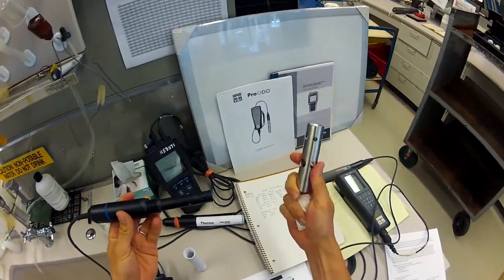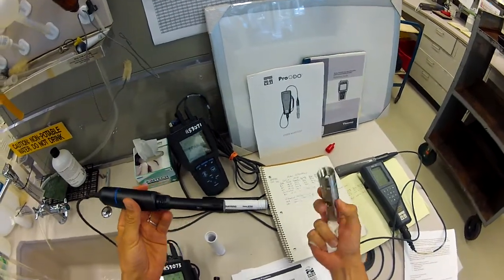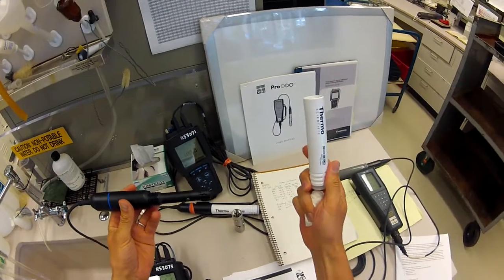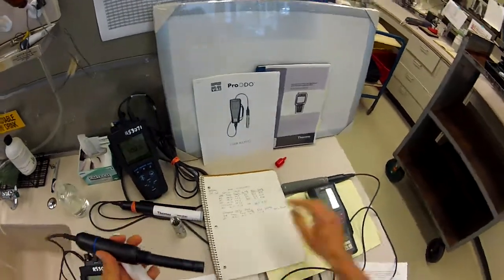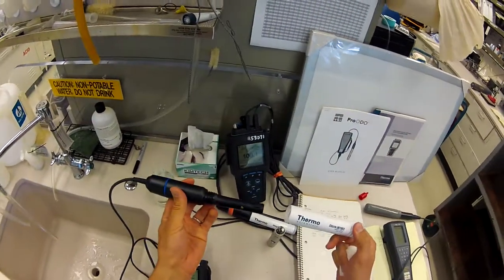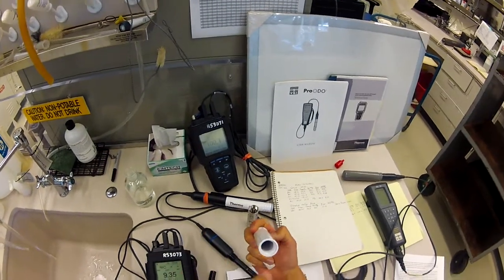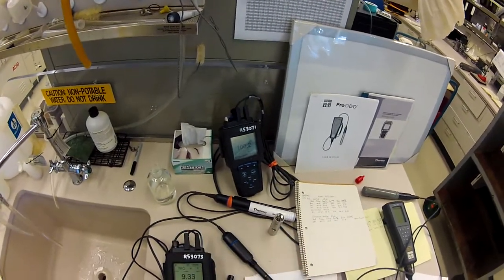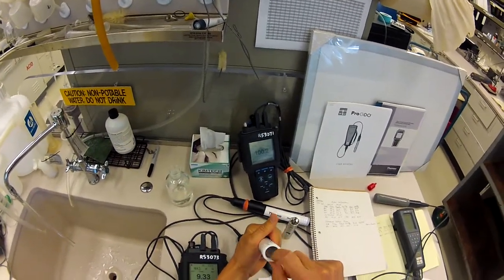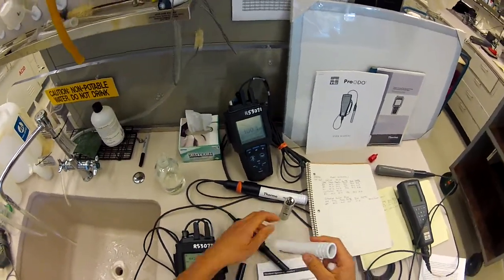The probe will usually have some type of guard to protect it during field use and then the calibration chamber of some type. Here's the YSI calibration chamber, this gray end on that probe. The Thermo one looks like this, and the calibration chamber will usually maybe have some type of sponge in the end of it that you'll either be able to pound out or it'll have access from the end like this.